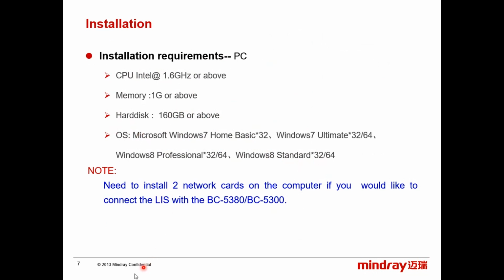This is a little bit older, the PPT, but no worries about it. You can install directly Windows 10. Then you must have 2 partitions. Leave C for the Windows and Windows application, and D leave it only for the Mindray software. Of course, if you need to connect the analyzer to the LIS system, you cannot connect it directly from the analyzer, but you need to connect first the analyzer to the computer through network card, let's say number 1, and then from the data management software of the analyzer, you connect to the LIS software through another network card.